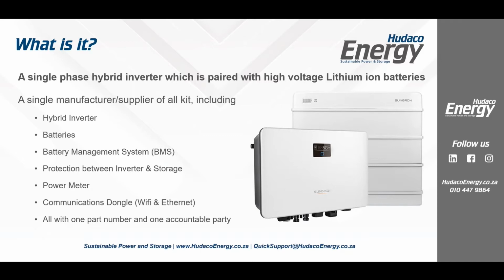So when you buy the kit, we have a single part number, and that part number comes with the hybrid inverter, the batteries in the size that you've requested, and a battery management system that allows the inverter and the batteries to communicate seamlessly together. It includes all of the protection between the inverter and the storage, so you don't have to go out and add a whole lot of other stuff. It includes a single phase power meter with a CT. It includes your communications dongle that you use for Wi-Fi and Ethernet. And all of it comes with one part number.